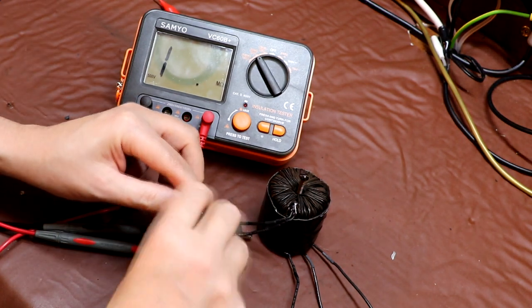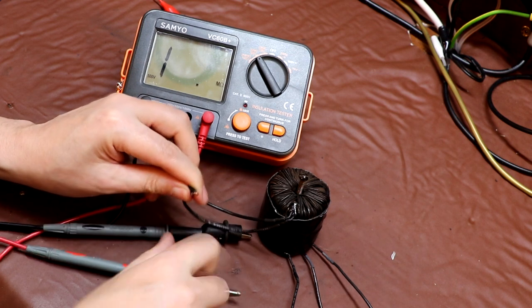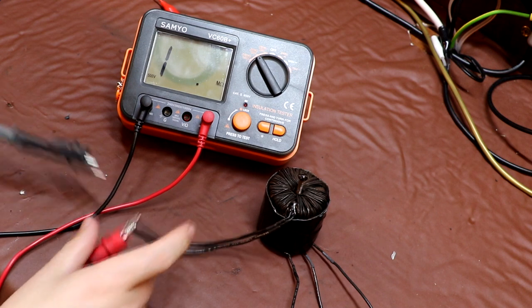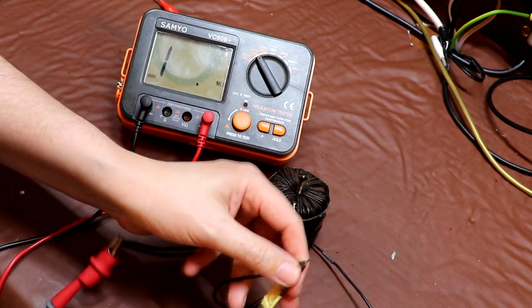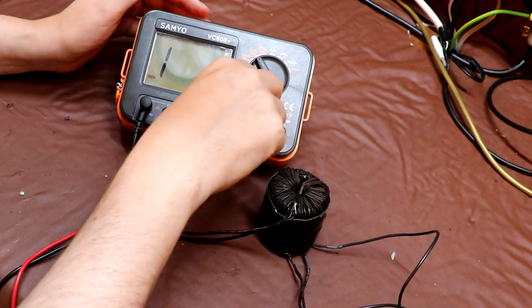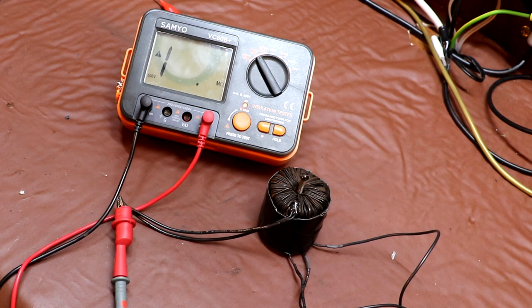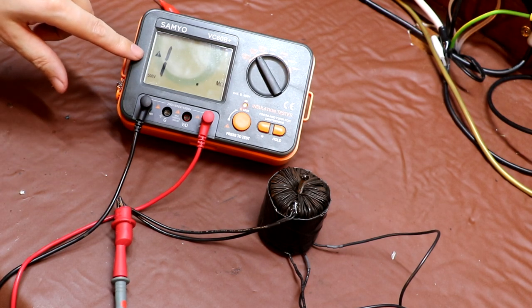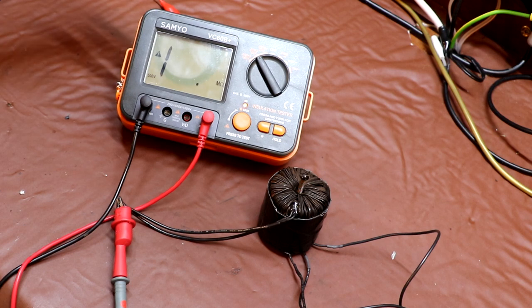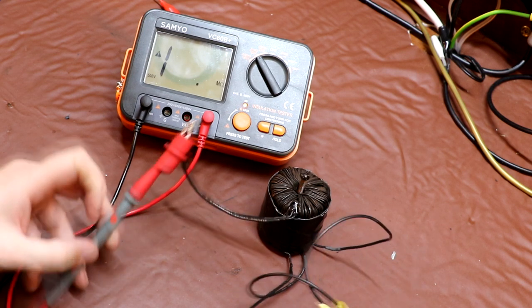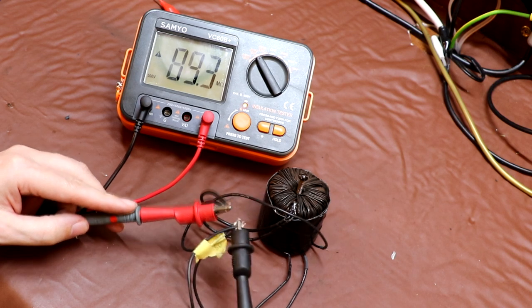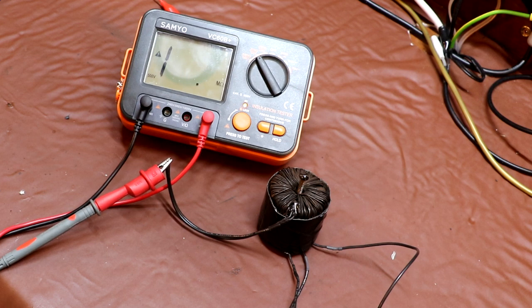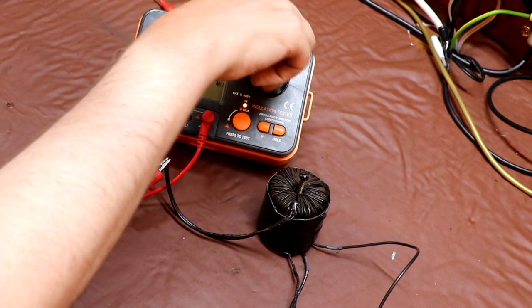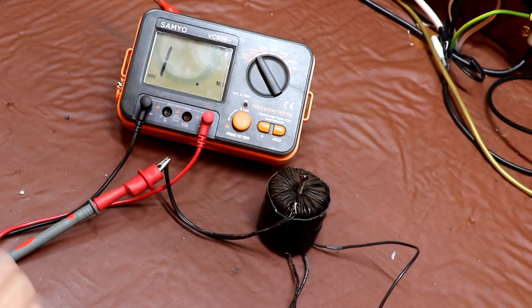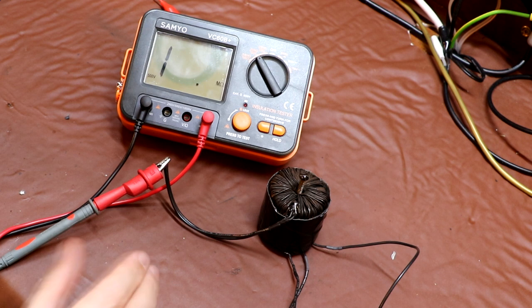So what I'm going to do is short the 2 secondary wires together, and then ideally we would do the same with the primaries, and then turn the meter on and hope for a high reading. Okay, this meter's reading infinity, so it's clear we've got no conduction between the primary and the secondary. I always like to confirm that the equipment's reading right, so let's bring the leads together. Okay, so we know the meter's good. Turn the meter off so I don't get an electric shock. So that was an insulation resistance test between the primary and secondary.